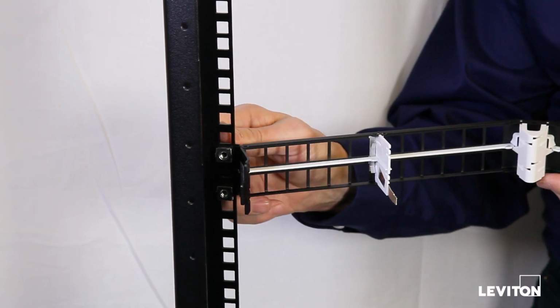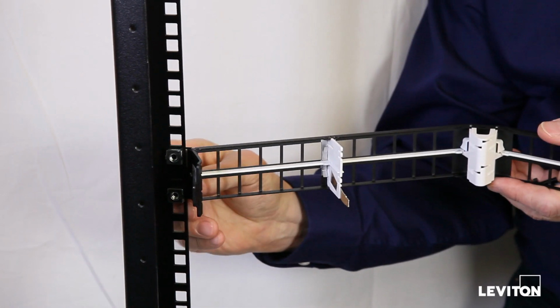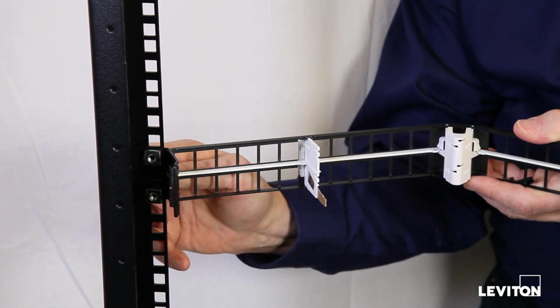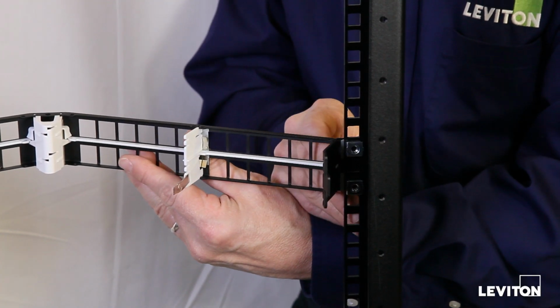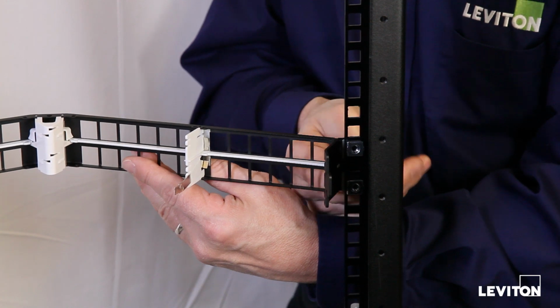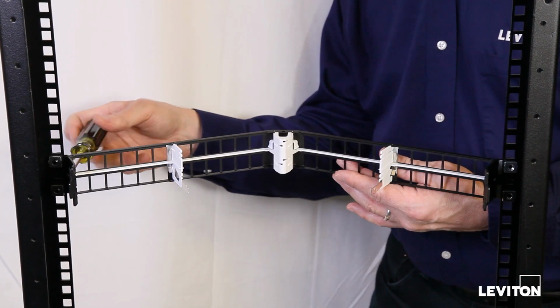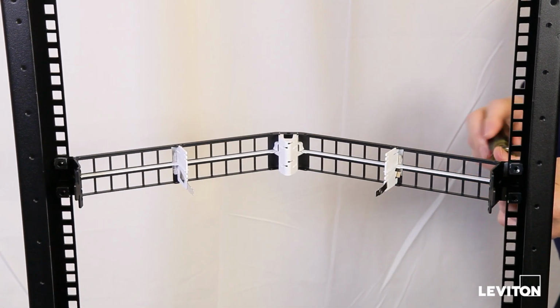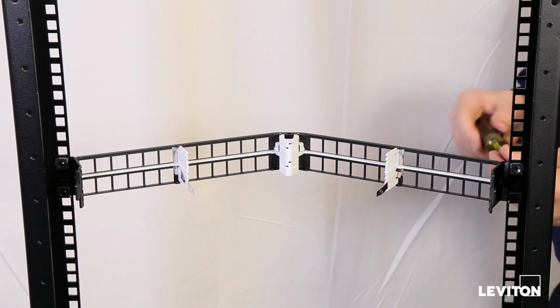Begin by inserting the cage nuts in the appropriate holes in the rack. Insert the mounting screws into the cup washers. Rack the panel by twisting the screws into the cage nuts by hand, then tightening with a screwdriver. The mounting process is the same for the flat panel.